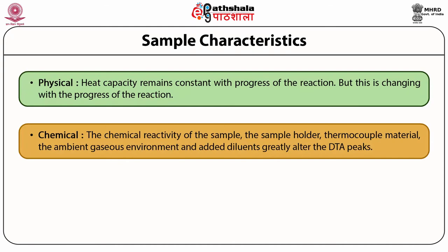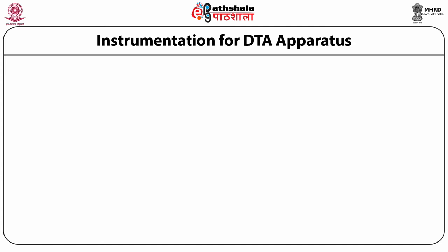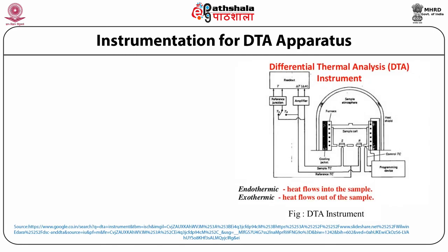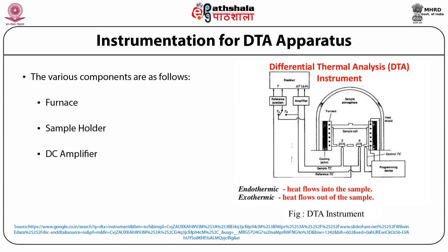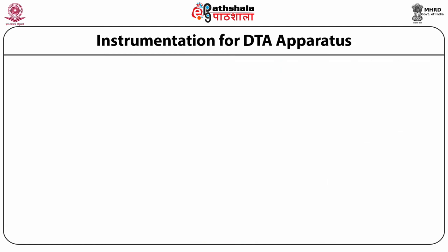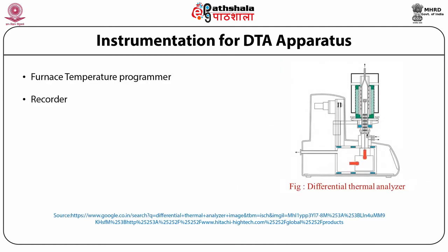Chemical changes: chemical reactivity of the sample, sample holder, thermocouple material, ambient gaseous environment, and added diluents greatly alter the DTA peaks. DTA instrumentation: a large number of different instrument types are available for DTA studies. The DTA apparatus has various components including a furnace, sample holder, DC amplifier, differential thermal detector, furnace temperature programmer, recorder, and control equipment.